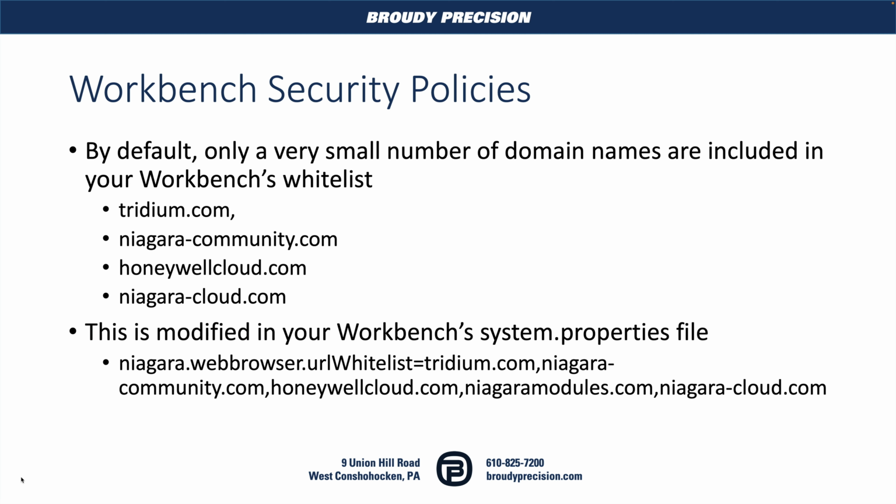So by default, only a very small number of domain names are included in this whitelist. They are Tridium, Niagara Community, Honeywell Cloud, and Niagara Cloud. All of these URLs are used for various features, mostly the cloud-related features to get your device enlisted in the cloud services.